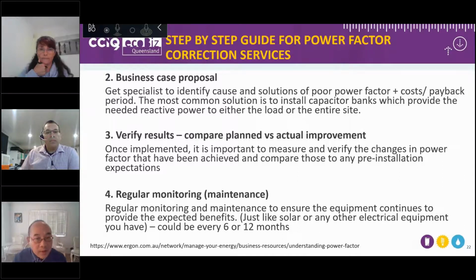So step 3, once you've got the business case proposal and it does stack up, once you've implemented the correction, then actually measure the actual improvement in power factor versus what was the proposed improvement from the business case. And make sure that the actual improvement is close to your proposed improvement, and if it isn't, check in with the specialist to see what other changes need to be done to improve power factor.